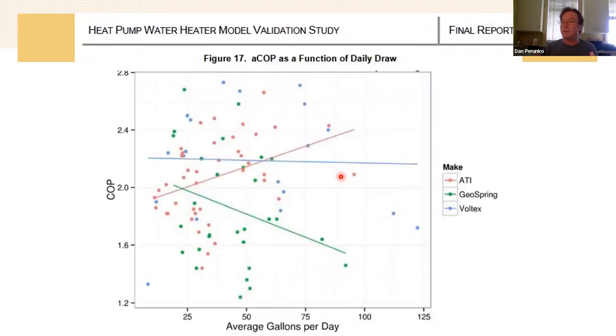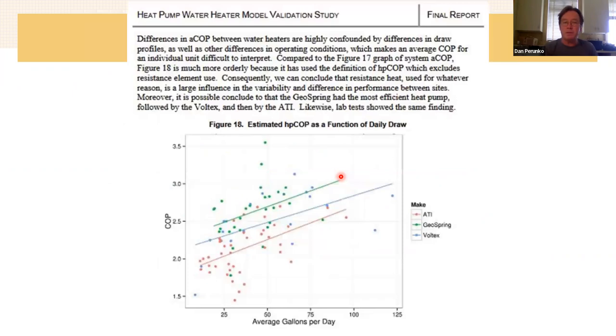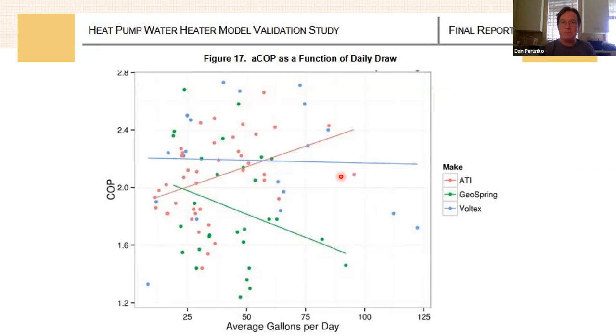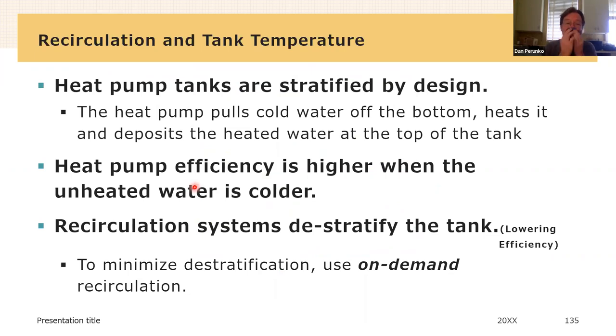This is what happens when you use electric resistance heat. To get the same amount of water out of the system in any given day, your electrical consumption goes way up and your efficiencies go way down. So most efficient operation is without electric resistance heat. Significantly less efficient operation, still better than an electric resistance water heater but not as good as it could be, is allowing electric resistance heat to continue to be used. This machine right there that didn't change has no electric resistance heat. So I said most of this already: the systems are stratified by design, cold water at the bottom, hot water at the top.